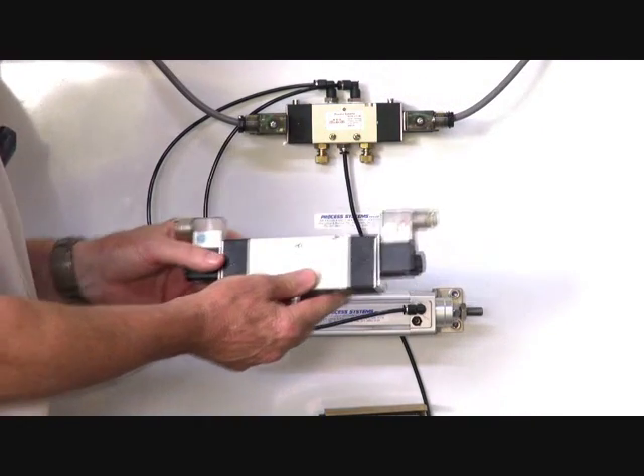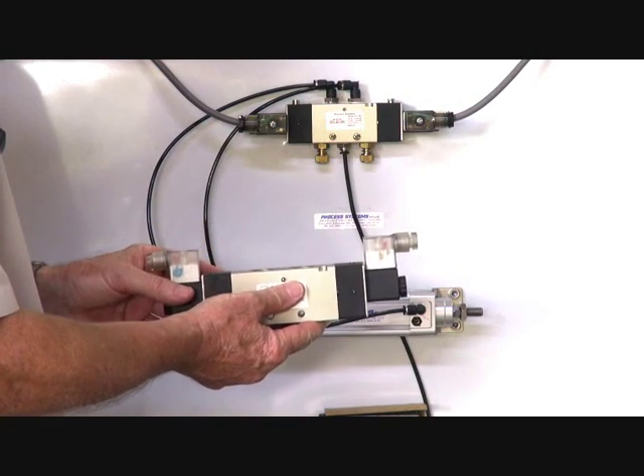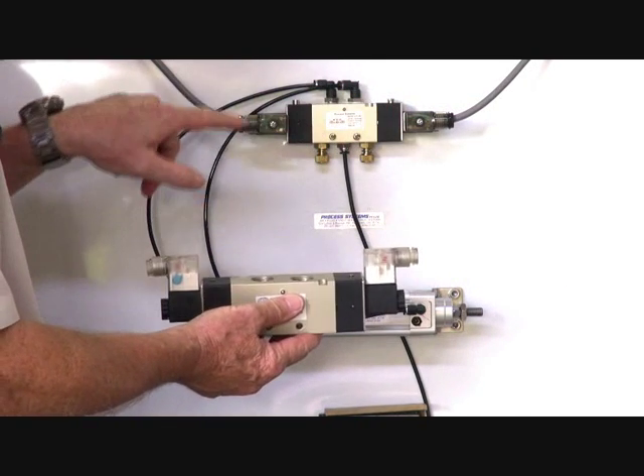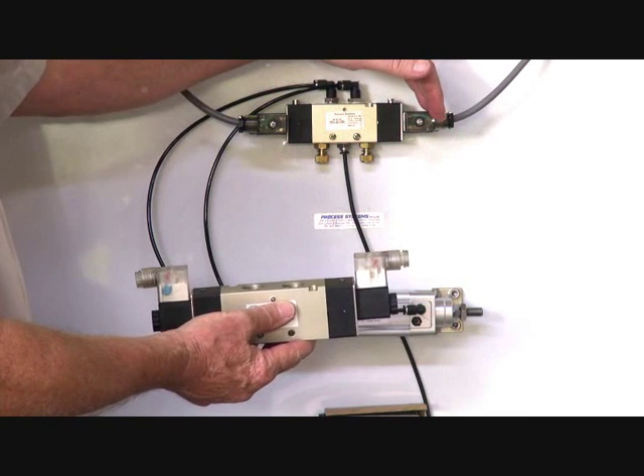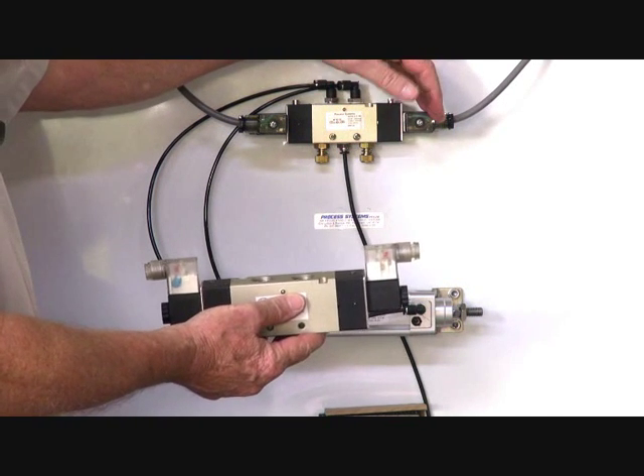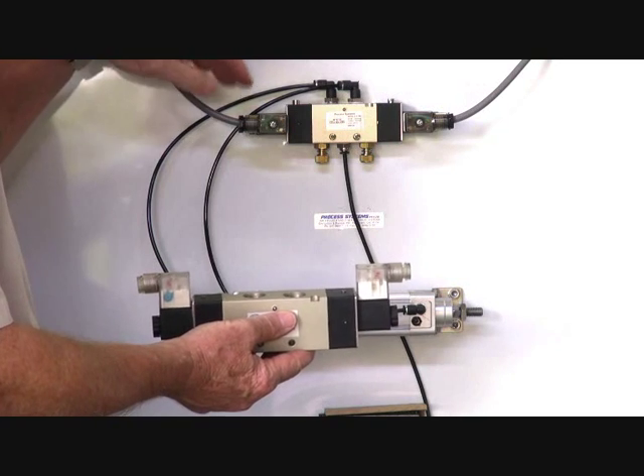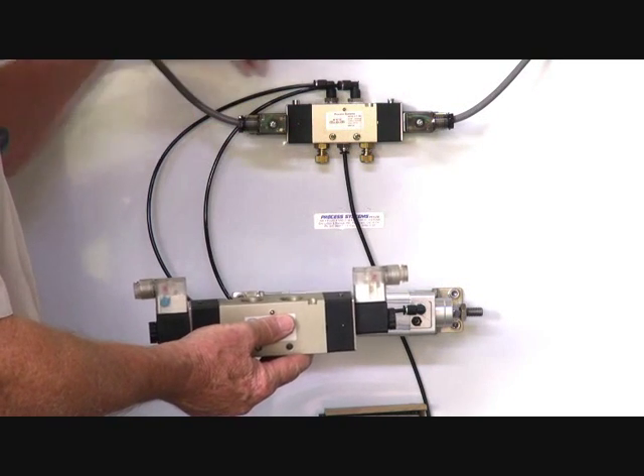It's a bi-stable valve, so you can have an electrical signal on one end or the other, and it'll hold it. Take the power off, it'll stay in that position. There's no spring in this valve. In the reverse situation, you put the pulse on the other end to switch it back again.